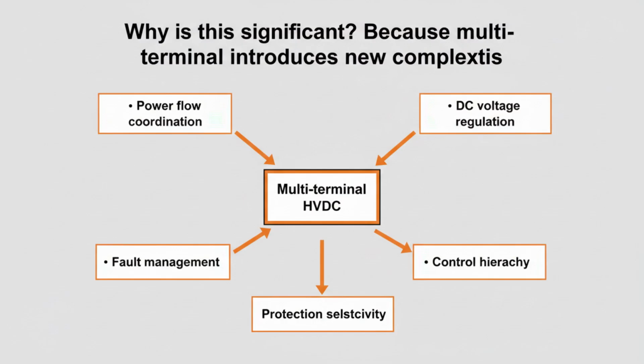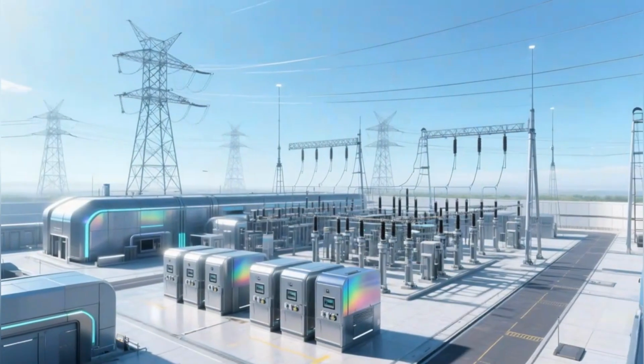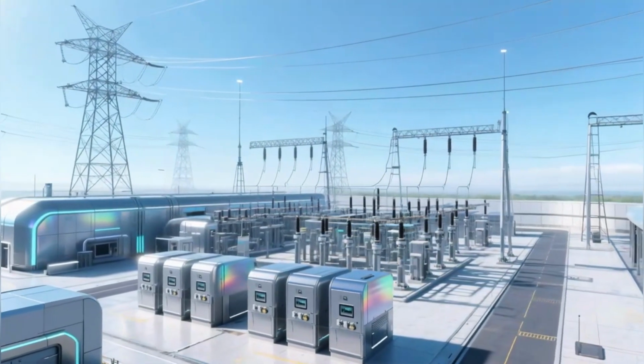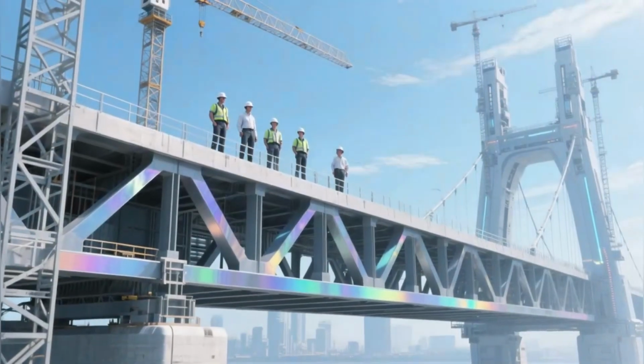Why is this significant? Because multi-terminal HVDC introduces new complexities. Power flow coordination, DC voltage regulation, fault management, control hierarchy, protection selectivity. In LCC systems, multi-terminal operation is particularly challenging because commutation depends on AC system strength. Converter interactions can destabilize control loops. DC fault clearing is not trivial. This project demonstrated that large-scale multi-terminal UHVDC is feasible in real operation. That was a major engineering milestone.